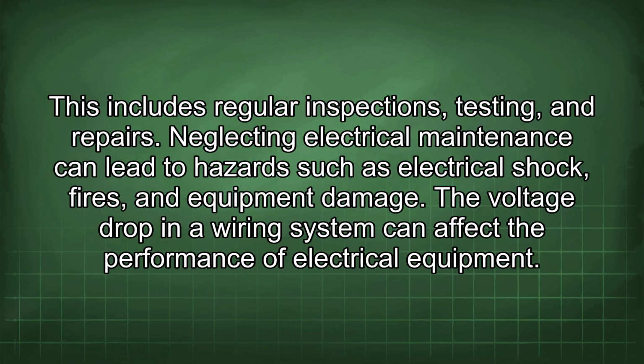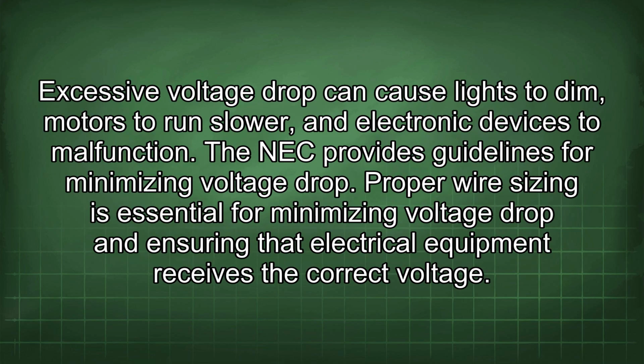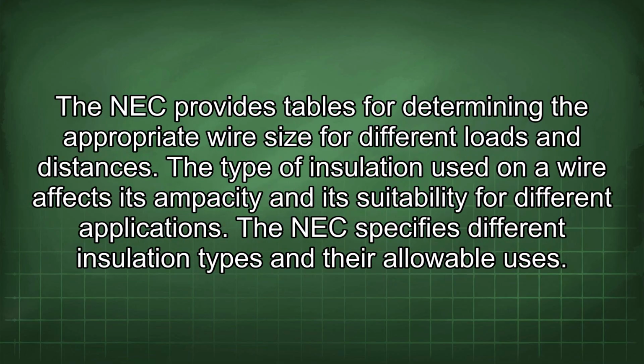The voltage drop in a wiring system can affect the performance of electrical equipment. Excessive voltage drop can cause lights to dim, motors to run slower, and electronic devices to malfunction. The NEC provides guidelines for minimizing voltage drop. Proper wire sizing is essential for minimizing voltage drop and ensuring that electrical equipment receives the correct voltage. The NEC provides tables for determining the appropriate wire size for different loads and distances.